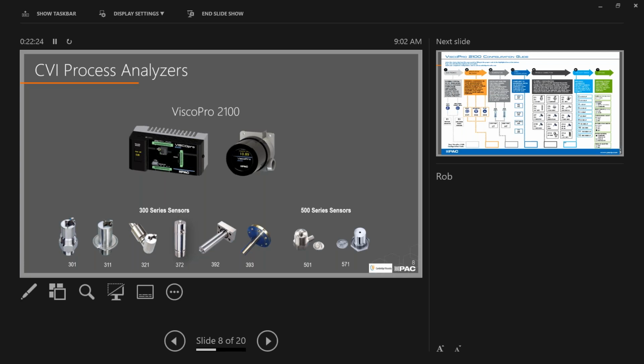The 501 and the 571 sensors are miniature sensors, if you will. These will fit in the palm of your hand. They're about the size of a 10-cent piece, about 12 millimeters in diameter, and these are used mostly in engines and compressor sumps, as well as test stands for compressor companies such as Carrier, Hitachi, Atlas Copco, and Danfoss. There's a limited viscosity range that can be read with these due to their small nature and a small gap. And with these, we can read up to 200 centipoise.